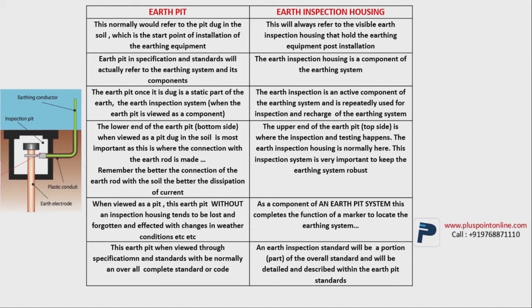So the bottom side of the earth pit, where you've inserted the rod in the ground, the connection between the rod and soil needs to be strong, for which we add a few chemicals. Once the lightning strikes, it should rapidly absorb the lightning within a few seconds. If not, it can lead to property damage. Therefore, the rod needs to be stuck in the soil firmly, whereas the top side of the rod is inside your inspection housing. From the top side only, we can check if the earthing is functional. We can be 100% sure of the working rate of the earthing only when we check at regular intervals.